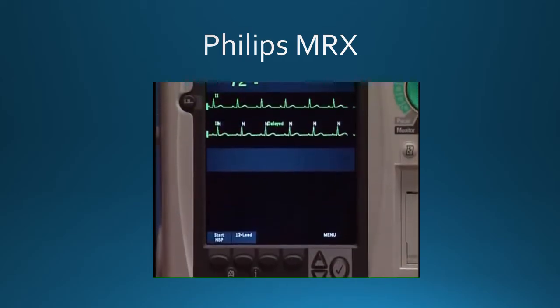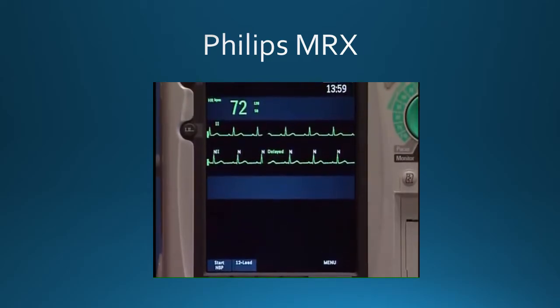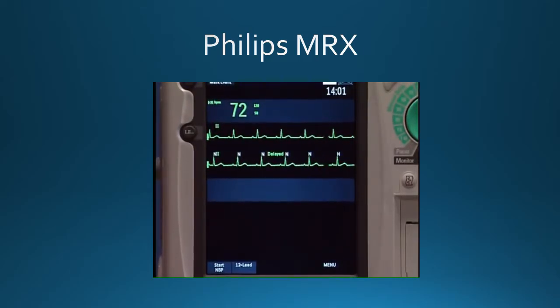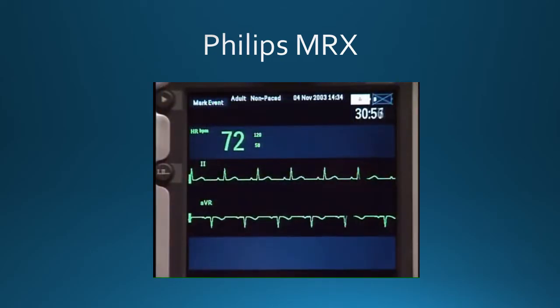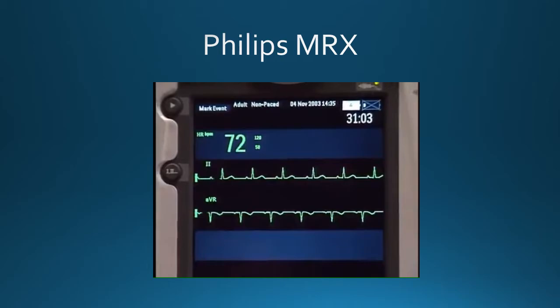The MRX uses the STAR basic arrhythmia algorithm for monitoring arrhythmia. It monitors pediatric and adult patients' ECGs for heart rate and ventricular arrhythmias and generates alarms. It specifically uses the ECG lead appearing in wave sector 1 for single-lead arrhythmia analysis. Note that increasing the wave size does not affect arrhythmia analysis.